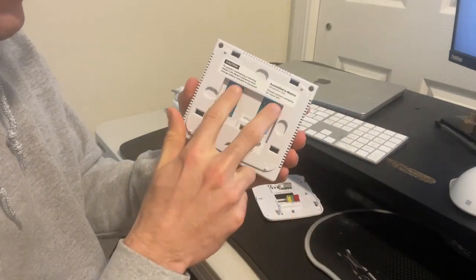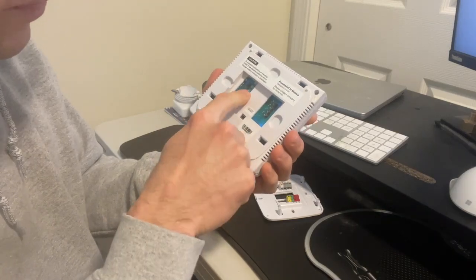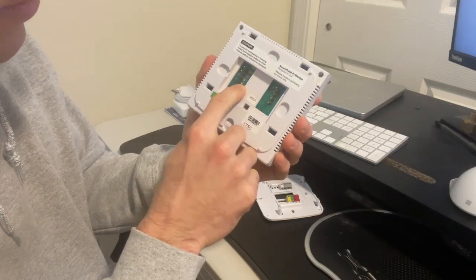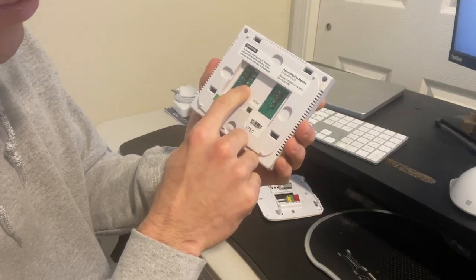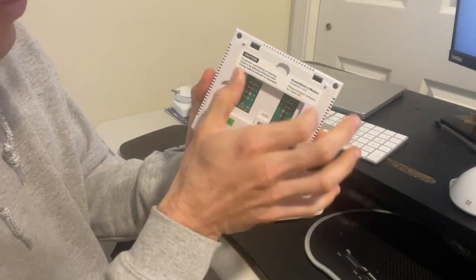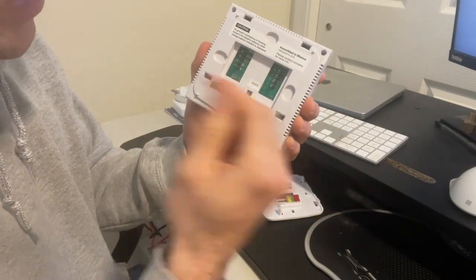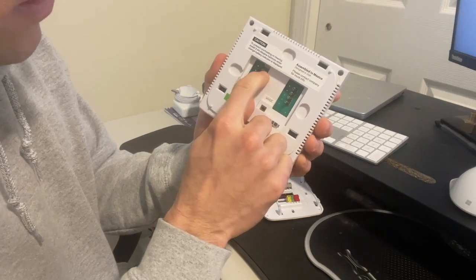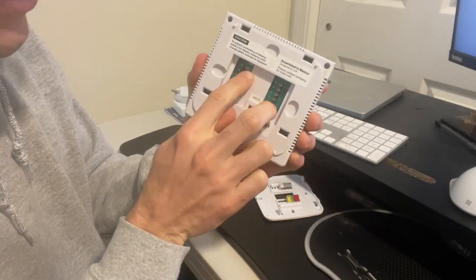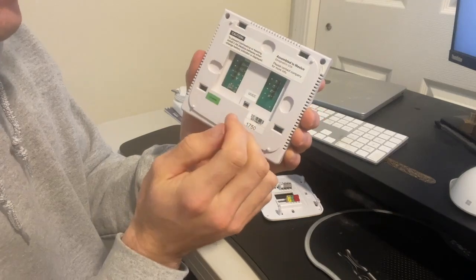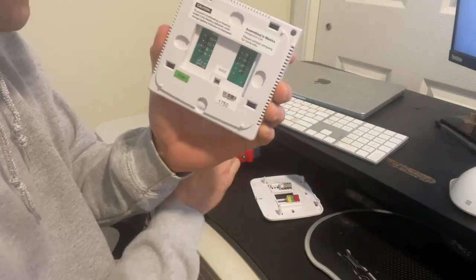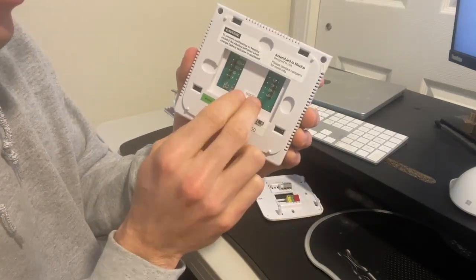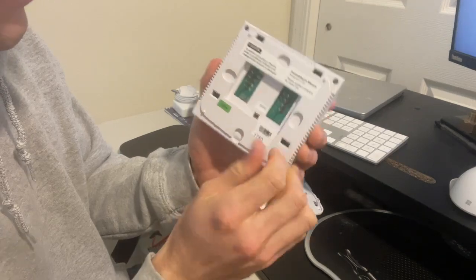And you can see these wires with the labels. So we've got an RH, an RC, a G, a Y, and a W. These are the ones that we care about right now. And so when you're heating, it's going to be RH and it's going to be making a connection to the W wire. And so we're going to be using that continuity mode to check if it is actually doing that.